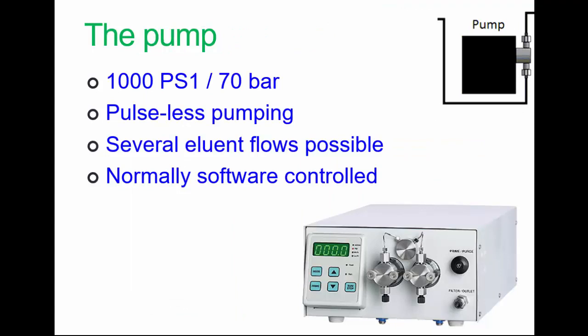The pump is the heart of HPLC. It mentions 1,000 psi, 70 bar. So 70 bar is about 70 times the atmospheric pressure. The pump is pulseless compared to, say, a peristaltic pump in a fish tank, which pumps and stops pumping. It also pumps at a very closely controlled rate, which makes the analysis possible. The process can be controlled from the pump by pressing various buttons, but it's almost always done using software control.